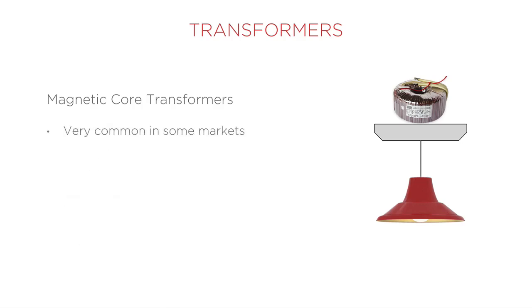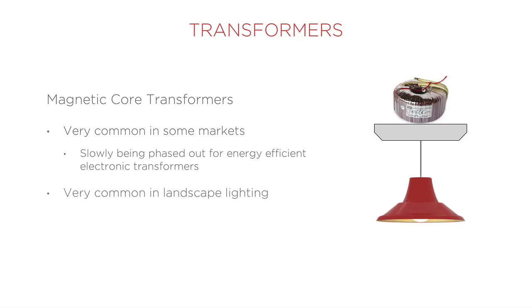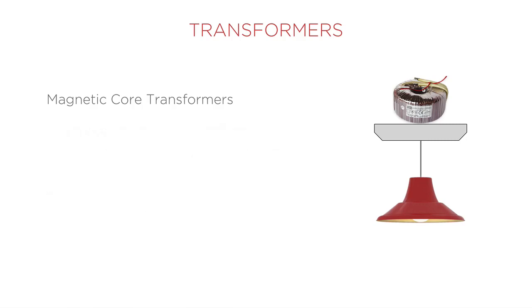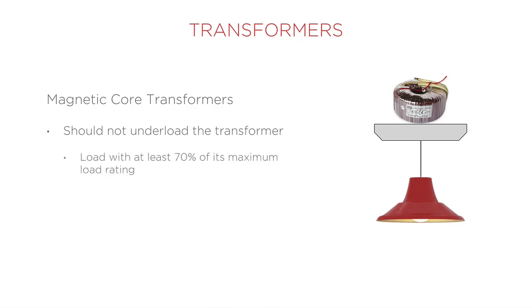Magnetic core transformers are very common in some markets, but they're slowly being phased out for the more energy-efficient electronic transformers. They are very common in older homes and in landscape lighting. These loads are generally not dimmable. When using a magnetic core transformer, you should never underload the transformer. It's best to load it with at least 70% of its maximum load rating. If rated at 600 watts, it should have at least a 420-watt load attached to it.